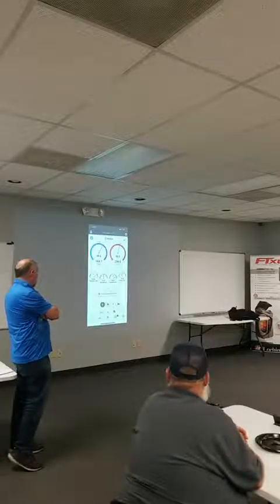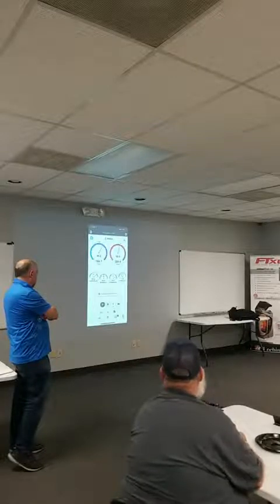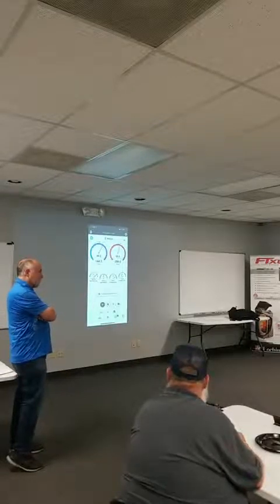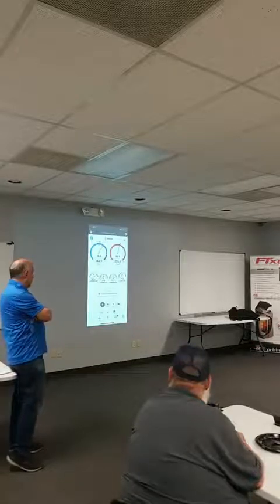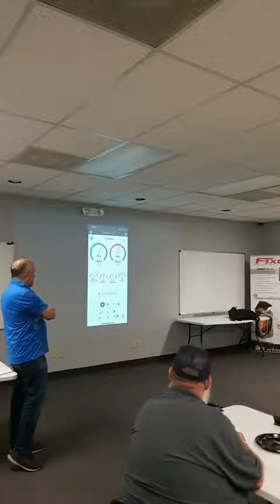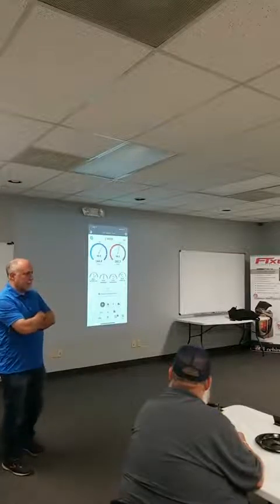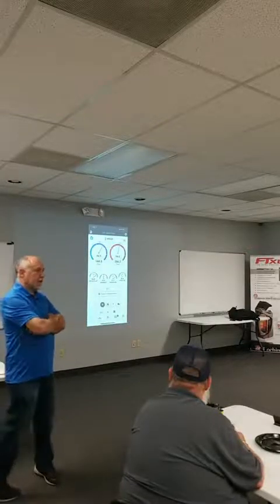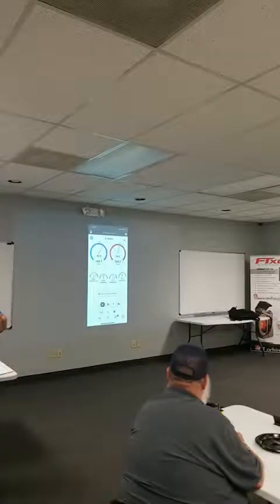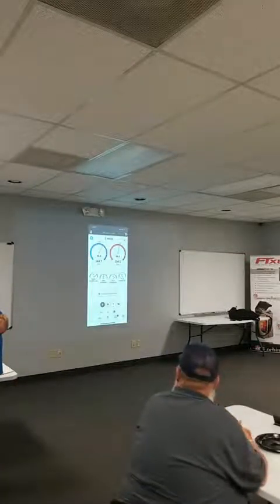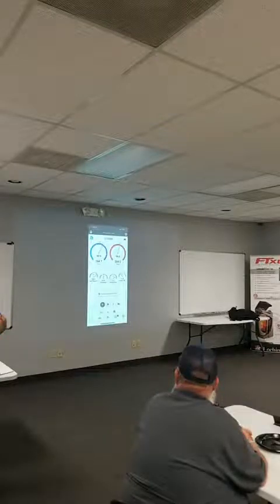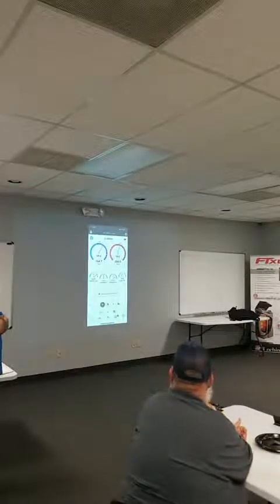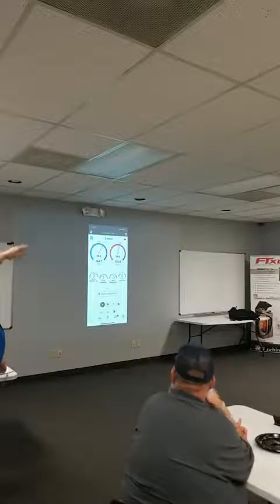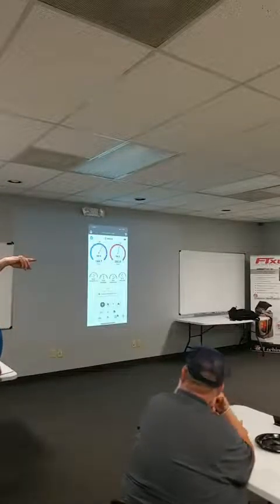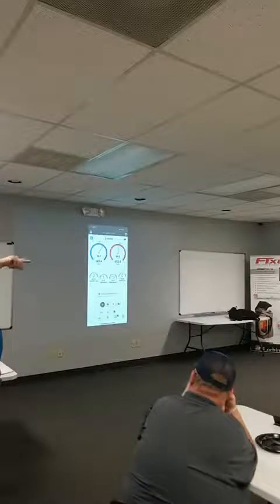Still runs pretty high suction line, some pretty high subcooling. So while we're waiting for that to stabilize, it went in the 20s when we did this originally. Now in this Trane unit, if that's a Trane unit anyways, what's the subcooling supposed to run on those roughly? 7 to 10 degrees is typical for a Trane on the subcooling, unless they have a subcooling circuit. Sometimes they do have a second one, you can actually see it. If you trace the condenser piping out, you'll notice that it goes down, usually 2 rows go into one, and it'll come out, and it'll be like the bottom part of the coils for a subcooling circuit.